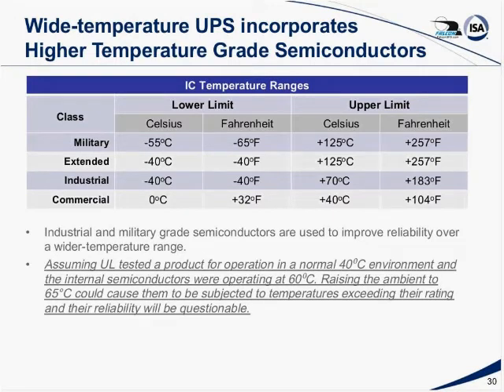Where that comes in, online UPSs generate heat through efficiency losses, and inside the case of the UPS, the temperatures can get elevated. Let's assume the UL tested product for operation in a normal 40 C environment, and the internal semiconductors were operating at 60 C. The rise in the ambient to 65 C could cause them to be subjected to temperatures exceeding their rating. Basically, you have to deal with that temperature rise inside the UPS that can be 10 to 20 degrees C, and still have the rating to, in the case of our SSD-RP, up to 65 C.